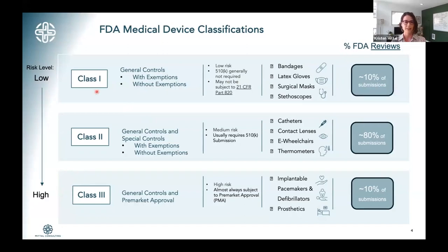Class one devices are very low risk devices, and usually they're exempt from having to submit a 510K submission. However, as with all classes of devices, general controls still apply. Types of class one devices would be bandages, latex gloves, surgical masks, stethoscopes—there's a wide range. In terms of the percentage of FDA reviews, about 10% of FDA reviews are for class one devices, and this is usually for the ones that require 510Ks. But while only about 10% of FDA reviews are class one, keep in mind that about 50% of the US market of medical devices is made of class one devices.